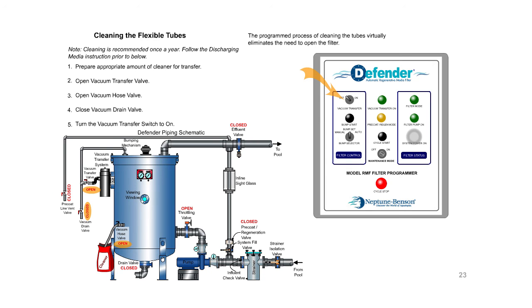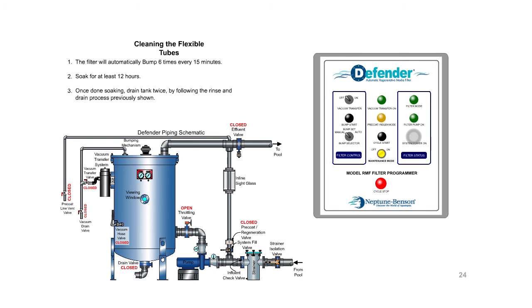Once you are done vacuuming in the cleaner, turn the vacuum transfer switch to off. Close vacuum hose valve and vacuum transfer valve. The filter will automatically bump 6 times every 15 minutes. Soak for at least 12 hours. Once done soaking, drain tank twice by following the rinse and drain process previously shown.